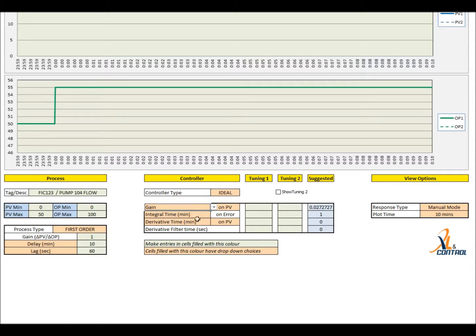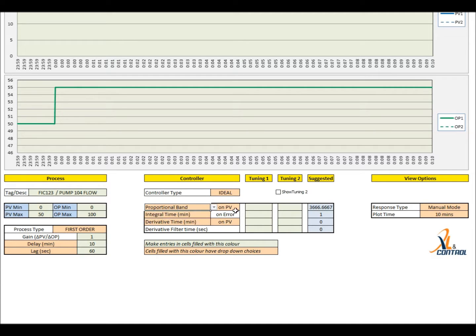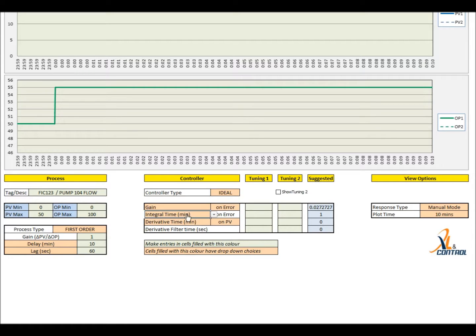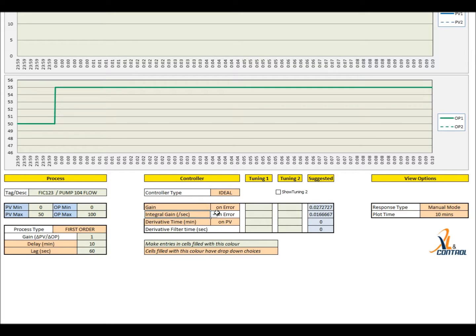The controller gain can be specified as proportional band or gain. Choose between proportional action on error or on process value. The integral term can be specified either as integral time or integral gain, with a choice of different units.